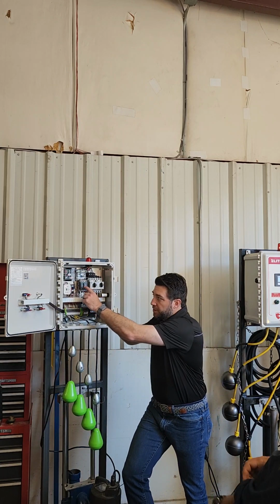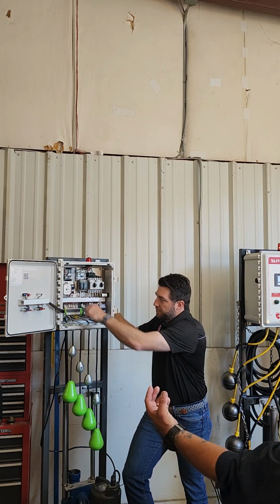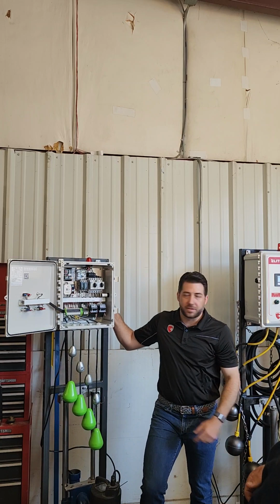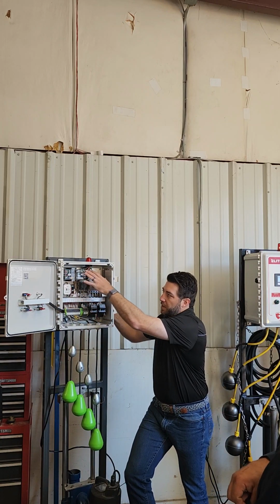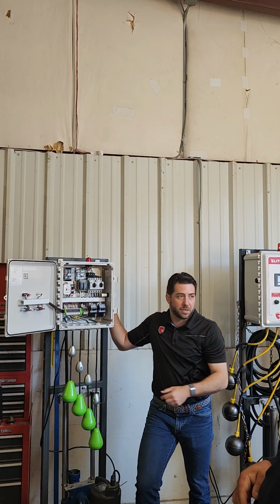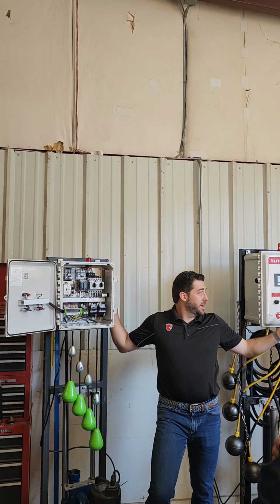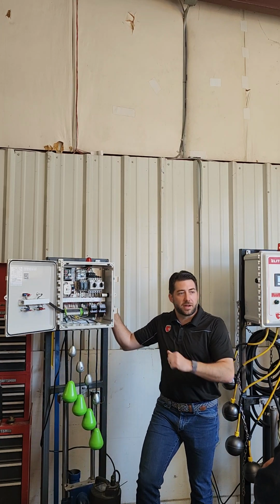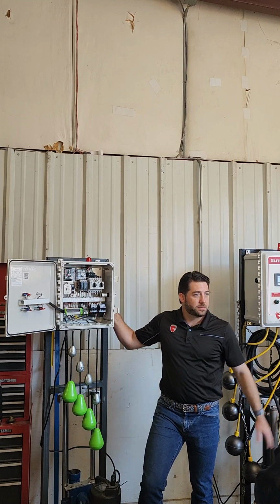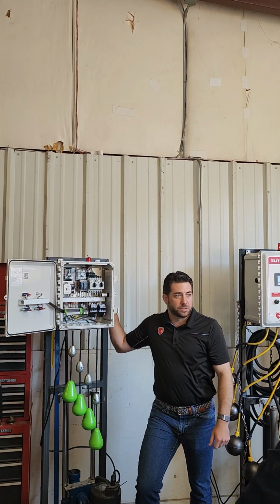And just because you're able to shut it off here, you still have live power coming in underneath. Okay, so that does allow you to make the rest of the panel safe, but there still is high voltage coming in. So just be aware, even when you have a through the door disconnect like this, if you're not shutting the power down ahead of the panel, you still have high voltage coming in.